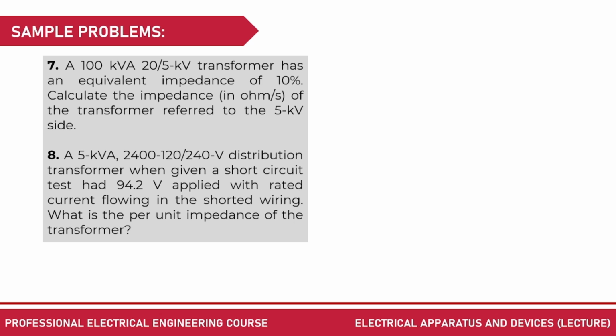Next is number 7. A 100 kVA, 20 down to 5 kilovolt transformer has an equivalent impedance of 10%. Calculate the impedance in ohms referred to the 5 kilovolt side. So that will be the secondary. The actual Z is Z per unit times Z base. Z per unit is 0.1 times a Z base of voltage squared, 5,000 volts squared, all over 100 kVA, 100,000 volt ampere.